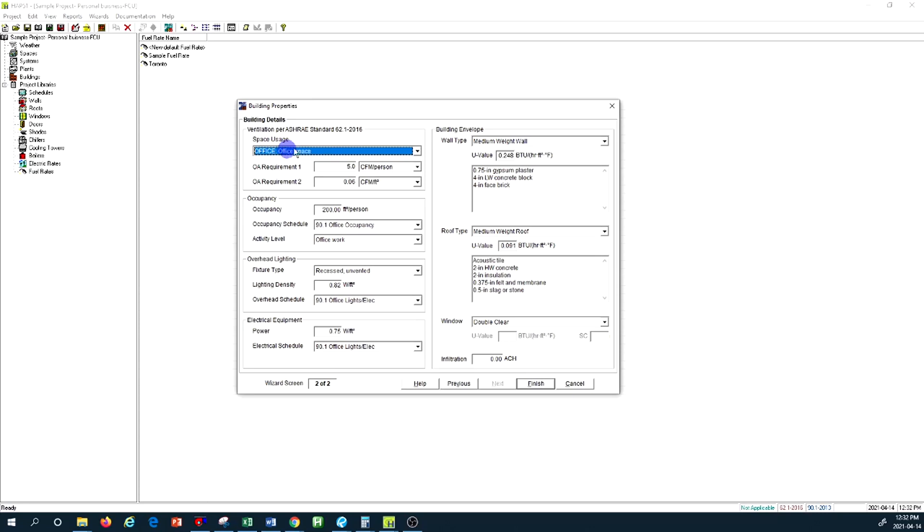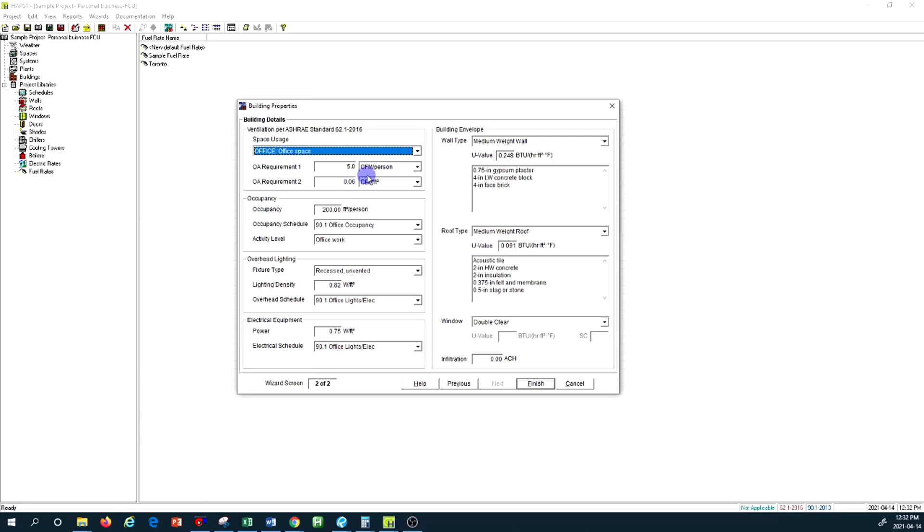But again, because this is a preliminary calculation we are looking at the dominant usage for the facility. So in this case, office. When you select that from the ASHRAE standard, automatically it selects what is the outdoor air requirement per person, CFM or cubic feet per minute of outdoor air per person, and also what is the rate of outdoor air per square footage of this type of occupancy.